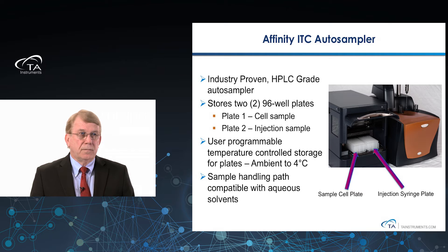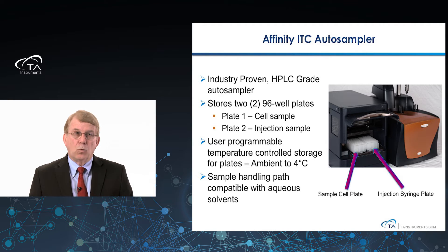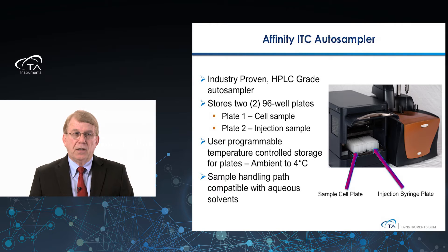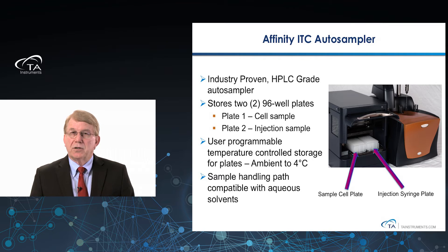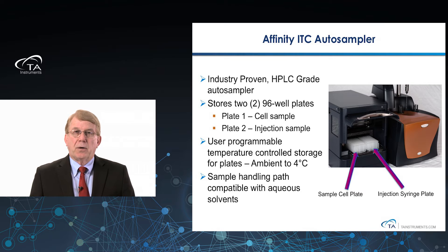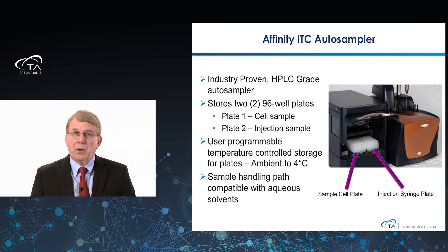The autosampler used is an industry-proven HPLC-grade autosampler. It has two 96-well plates — one for the cell sample and one for the injection sample. It is user programmable. The temperature-controlled storage area allows you to set the temperature from ambient down to four degrees for precious proteins that may be unstable at room temperature. The sample path is completely compatible with aqueous solvents as all ITC instruments are.